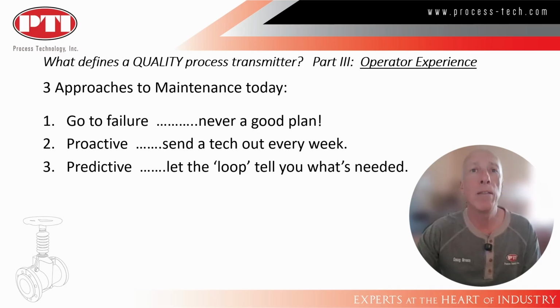Think about pre-9/11, that's 25 years ago. All you had was an error code displayed. No one knew what it meant, couldn't locate the manual to find out. Most of the time, it still didn't tell you what was needed, so you just replace the sensor and move on. Great for sales folks, bad for maintenance budgets.